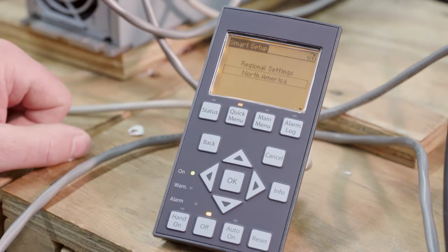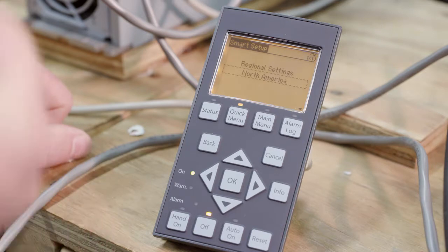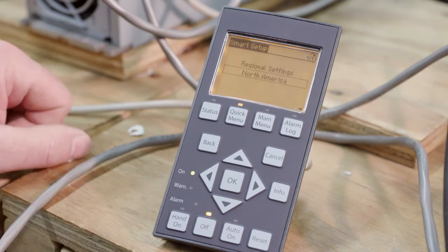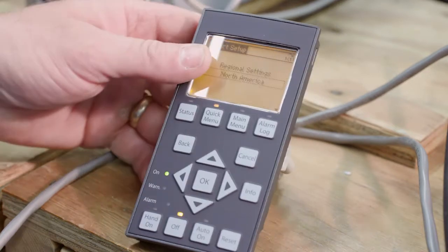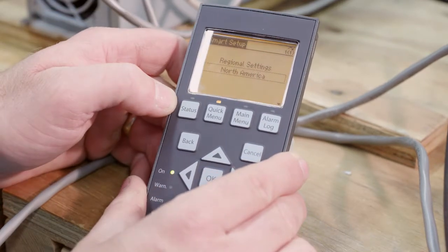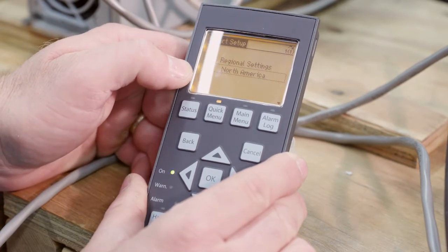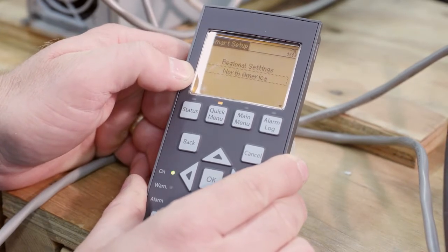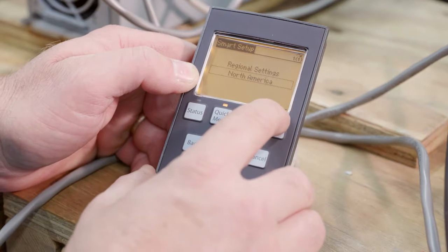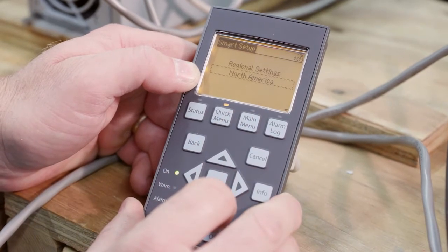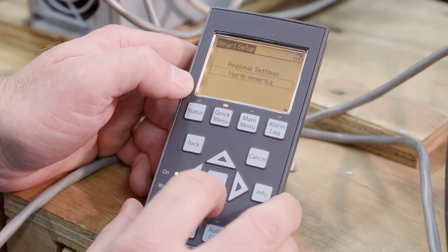If we find that it is going in the reverse rotation, you just want to flip two wires on the output on the motor side, and that's your U, V, and W terminals. So let's go through the smart setup here in this case. We're starting with regional settings, North America. You can see here I've got my arrow, which allows me to proceed.